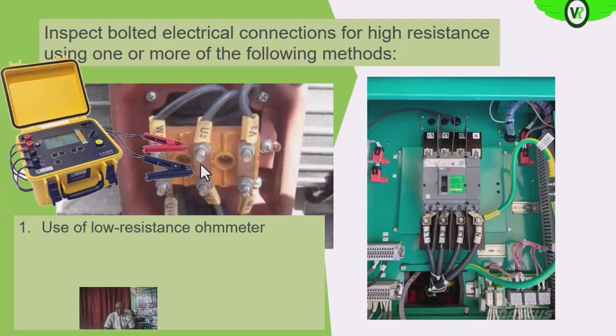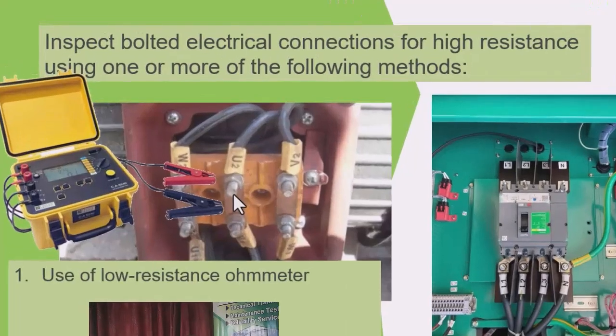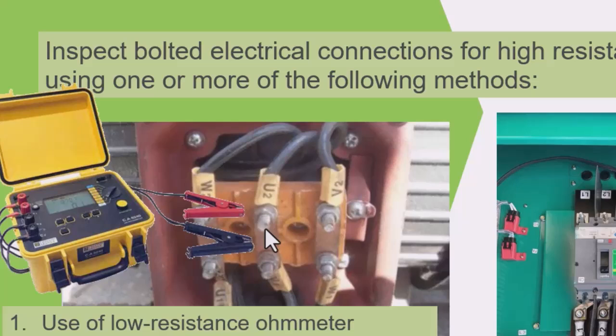Remember, current will flow through those terminals, and once the resistance is high, the I squared R effect will always come in, which means that there will be increased heat dissipation, which will eventually affect the efficiency of the electric motor, and even develop hot spots that can cause failure of the electric motor at that particular terminal.